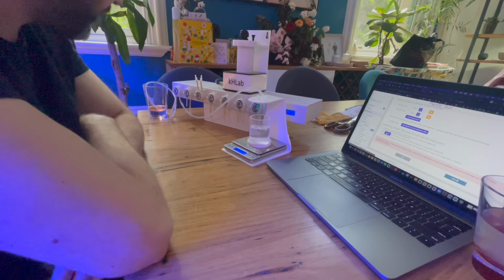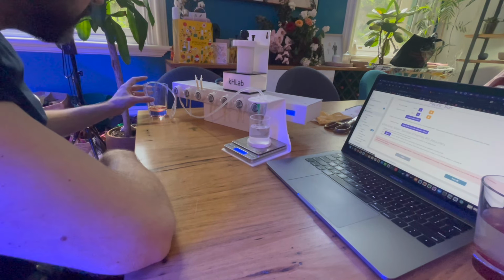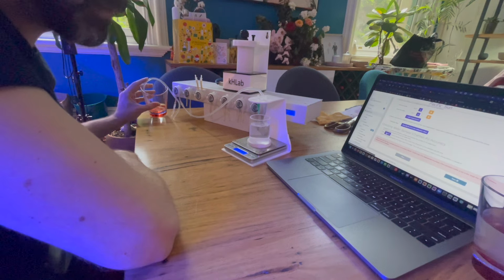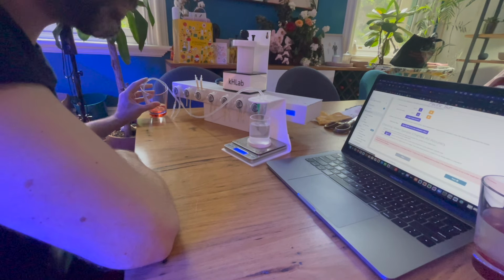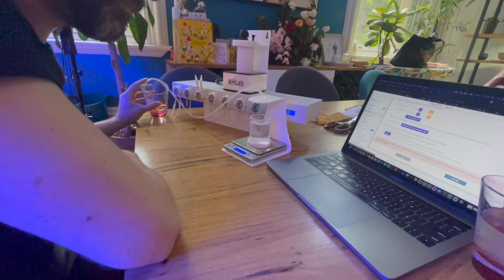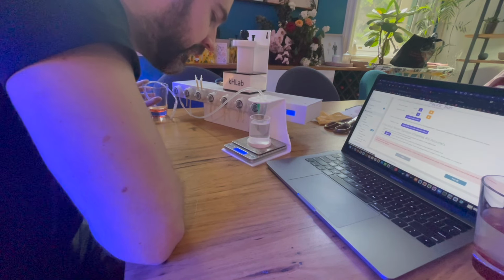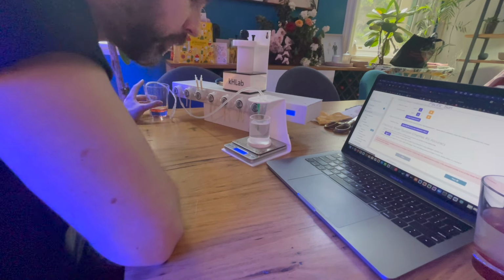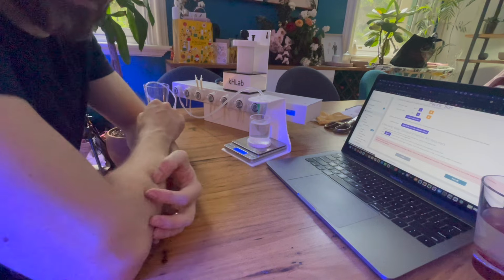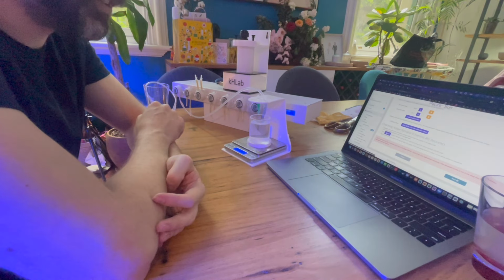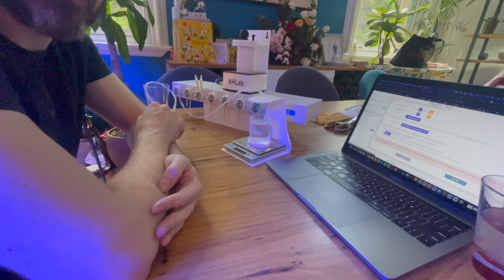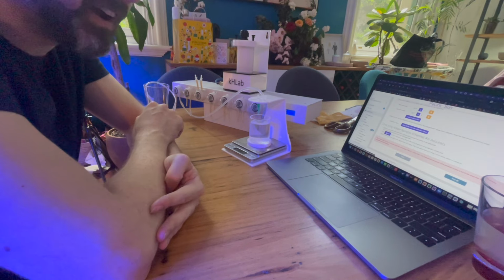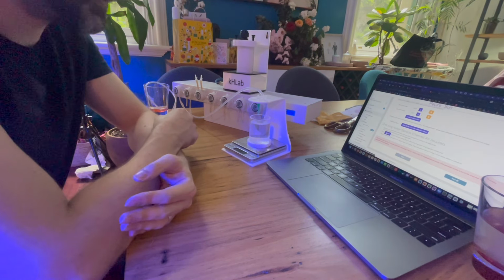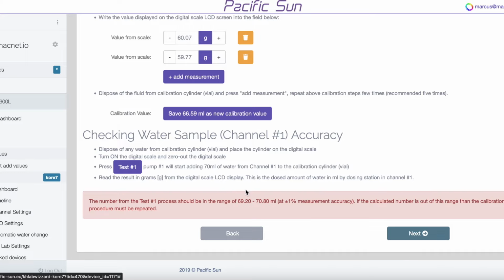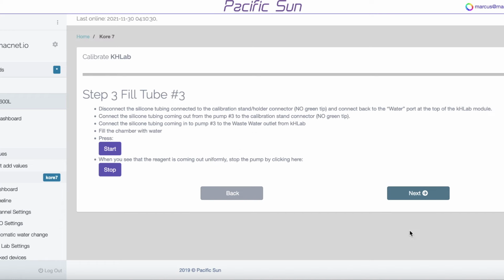Let's see how accurate it is off this final run, bearing in mind that I only gave it 2 values with which to calibrate. Boom, and the value is 70.02. So that calibrated really, really accurately off just 2 values, but as I said, I recommend you do 5. And yeah, it's as simple as that. You simply then go next on the screen here, and it will walk you through the process.